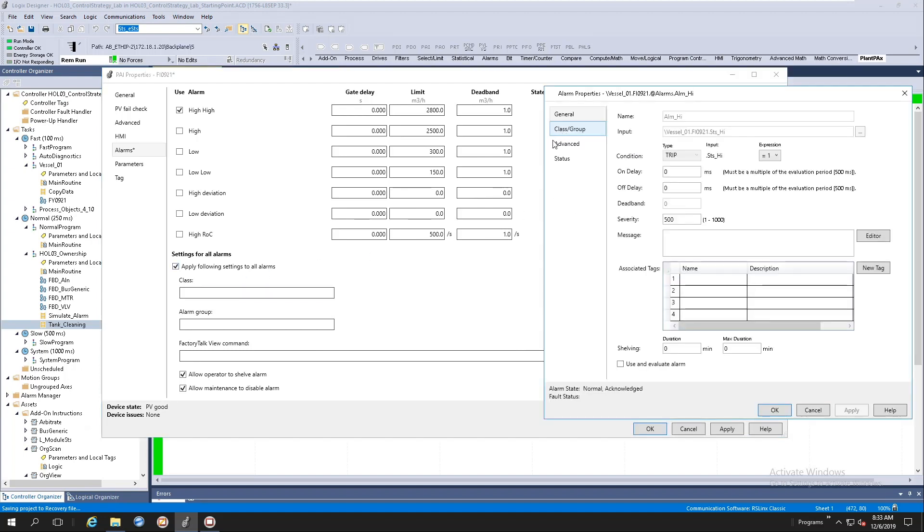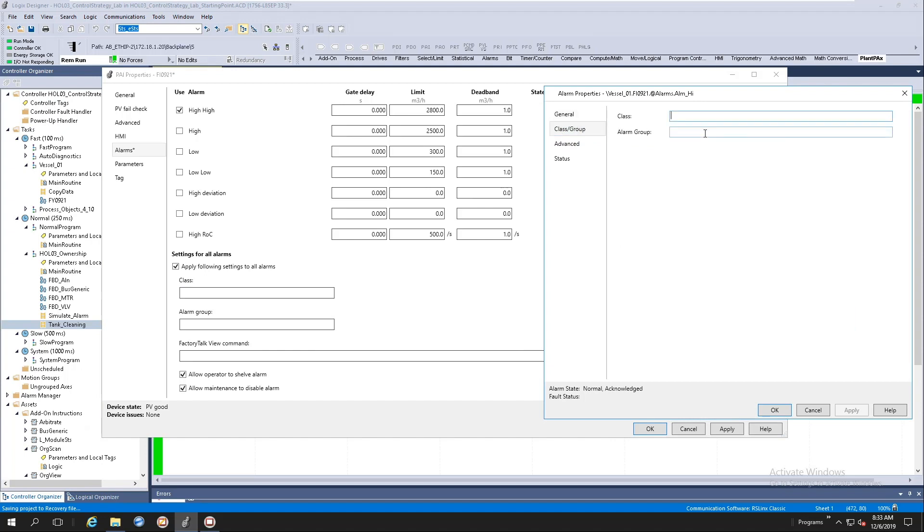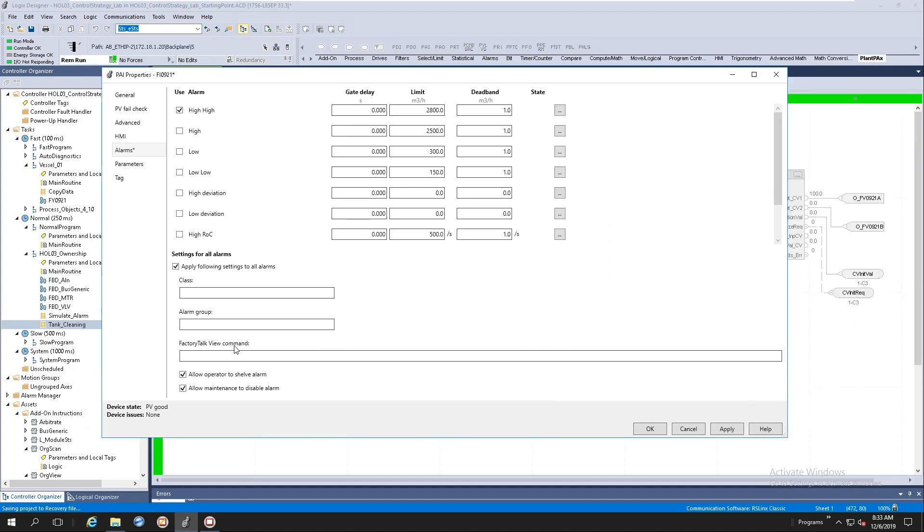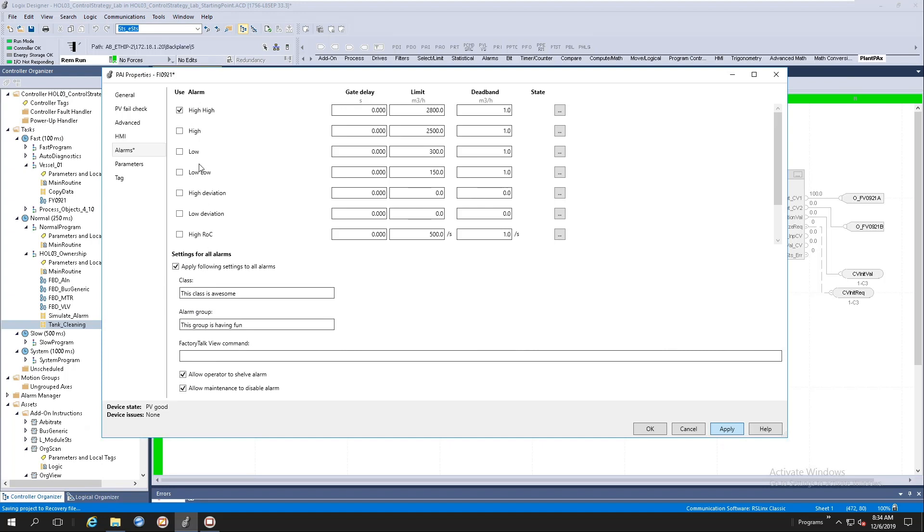Let's take the high alarm. I've got a class, and you'll notice that everything is empty. Okay, let's cancel here. And I'm going to say this class is awesome. And let's do the alarm group. This group is having fun. Right. Now if I hit the apply button, it will propagate all these values to all eight of the alarms here at the top. Once the application has been completed, it will uncheck the box here until you decide you want to propagate all the alarm settings to all the alarms again.